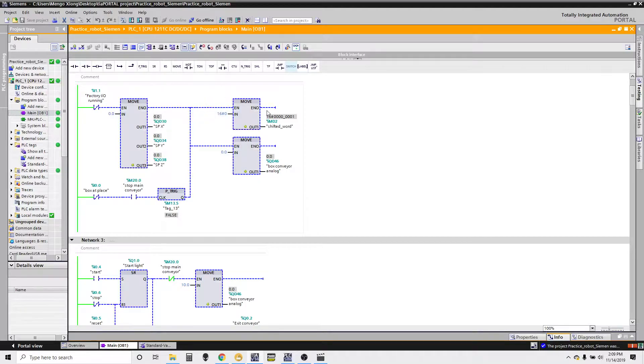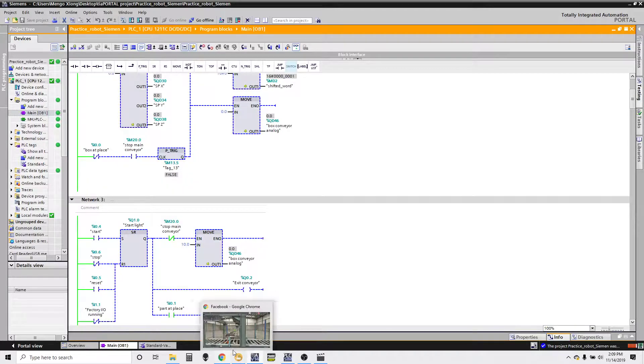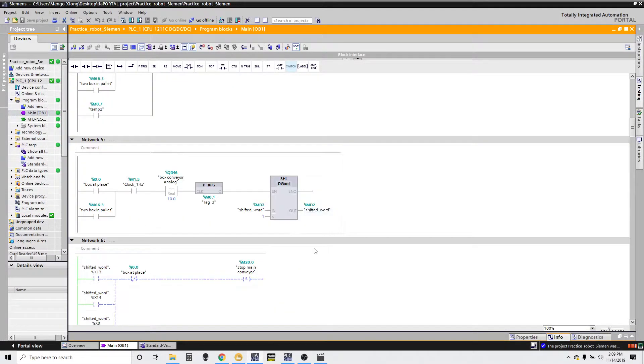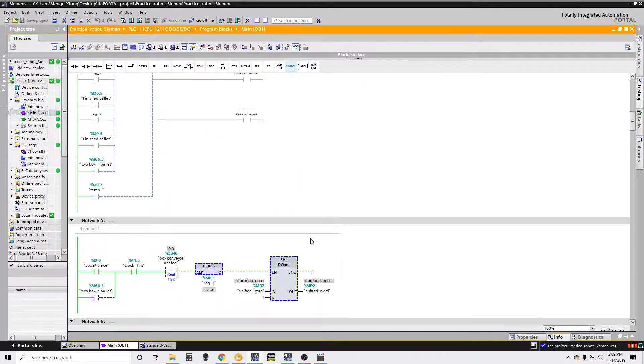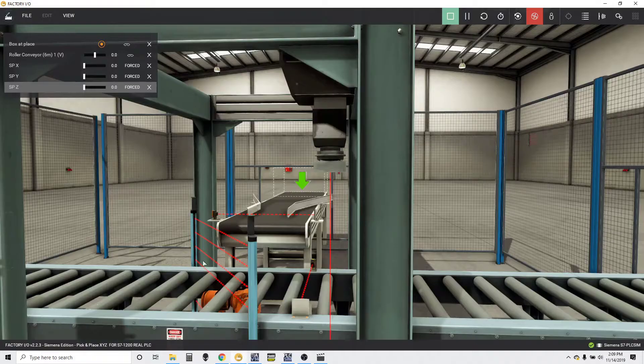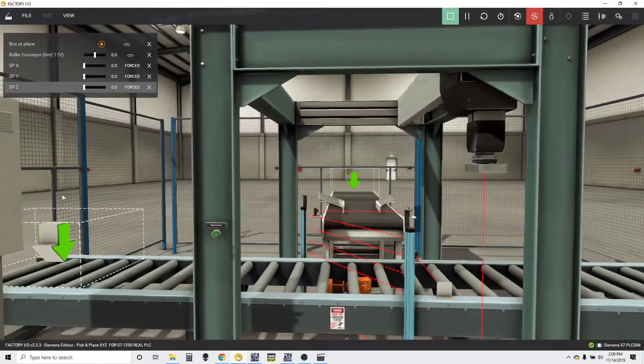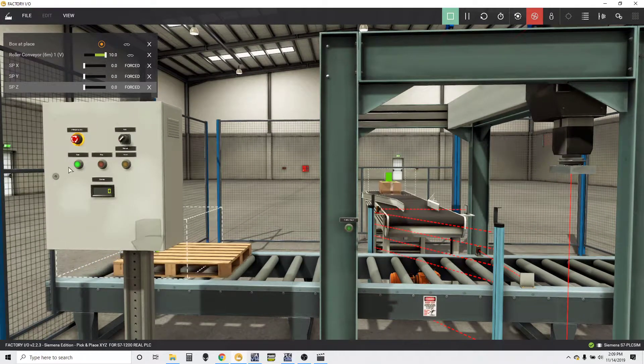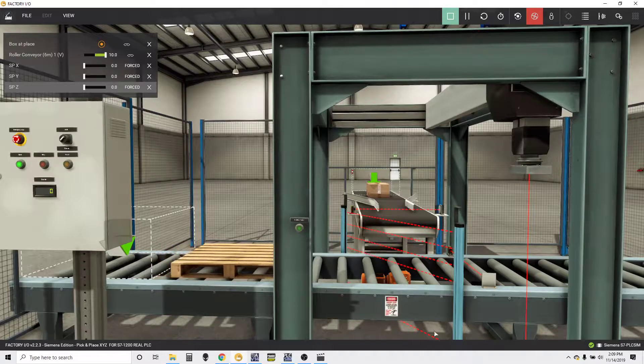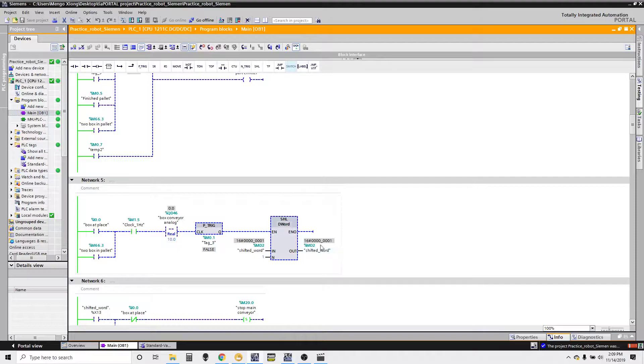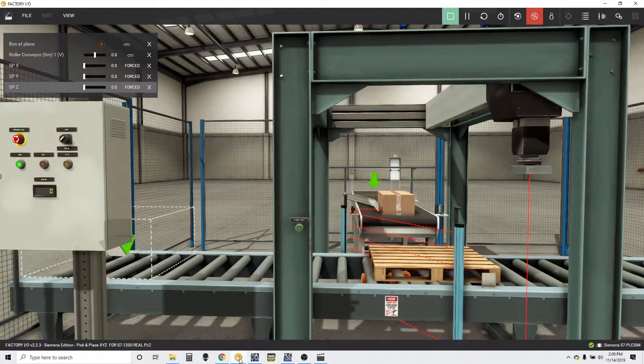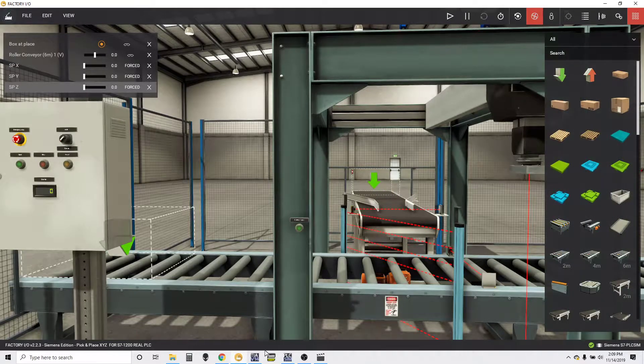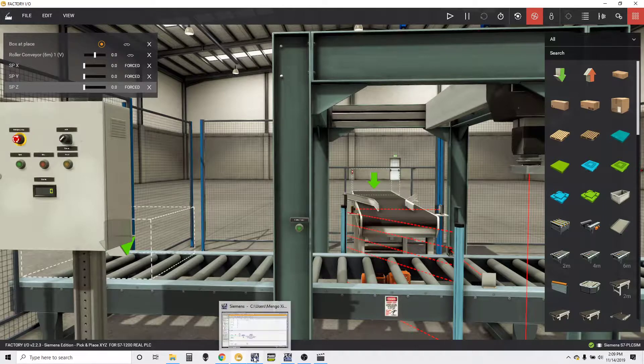I'm going to basically start the pallet first. What's unique about this logic now is I'm actually tracking the conveyor. I'll show you—once I press start right here, I'm actually tracking it with the shift register right here. As you can see, it's moving every single bit to the left, and I'm tracking the pallet every...